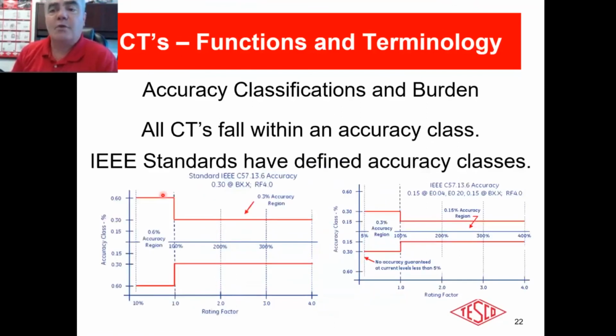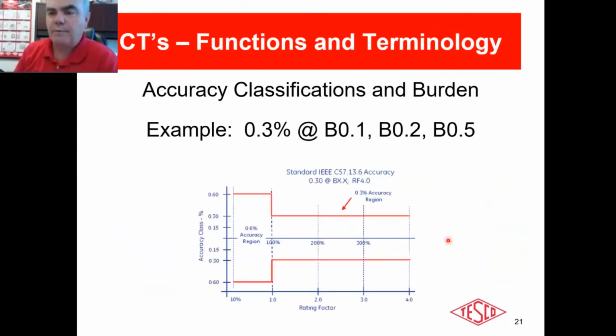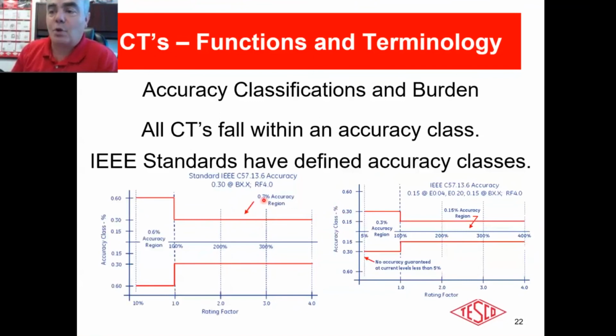All right, the extended ranges, and I threw up, this is an older slide. The extended ranges do two things. First of all, they're more accurate, 0.15, okay? So if this is, again, I'll pick on a 400 to 5. If this was a 400 to 5 with a thermal rating factor of 4.0, from 400 up to 1600, it's actually good to 0.15. So it's double the accuracy of the normal one. Actually, I've got it right here. Sorry. Double the accuracy of the normal one.